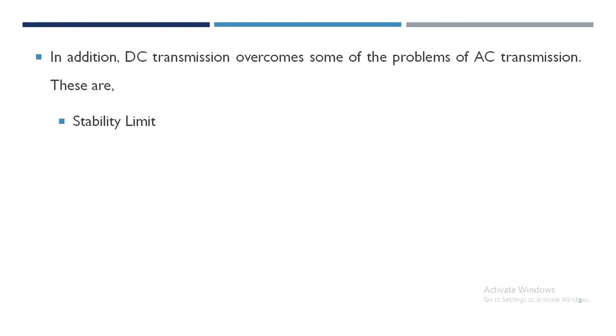This figure shows the power carrying capacity of AC lines as a function of distance. You can observe that as the distance increases for the AC network, the power is going to decrease. But for DC, it is shown with the dotted line. It means as the distance increases, the power for DC networks remains nearly constant. The same figure also shows the power carrying capability of DC lines, which is unaffected by the distance of transmission, and it is limited only by current carrying capacity of the conductor, which is termed as thermal limit.